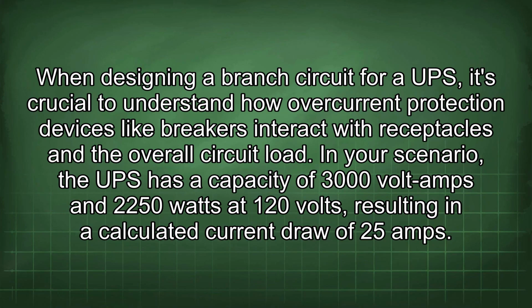When designing a branch circuit for a UPS, it's crucial to understand how overcurrent protection devices like breakers interact with receptacles and the overall circuit load. In your scenario, the UPS has a capacity of 3000 volt amps and 2250 watts at 120 volts, resulting in a calculated current draw of 25 amps.